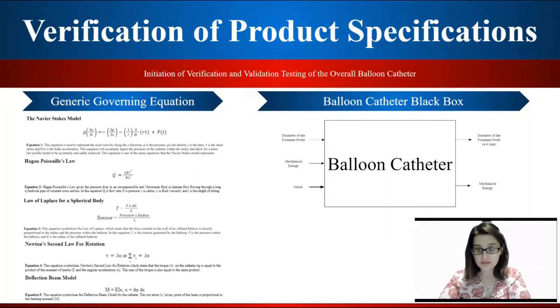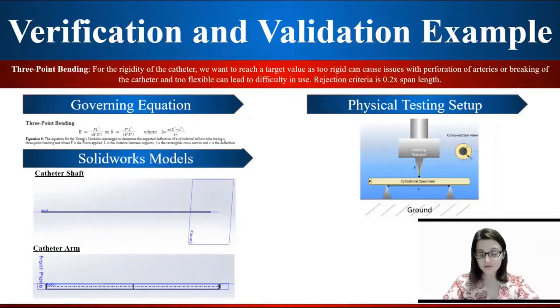To initiate our verification and validation testing of the overall balloon catheter, we started with a generic black box approach that was then split into 5 different parts using the equations found to the left. We then delved further into these using both physical and virtual testing methods. An example of our prototyping activities includes a 3-point bending test to test for the rigidity of the catheter tube. This has a very clear rejection criteria of 0.2 times the span length.